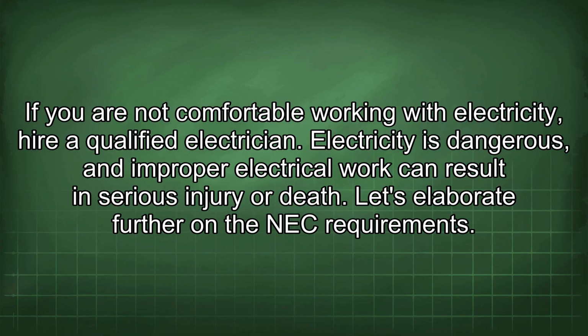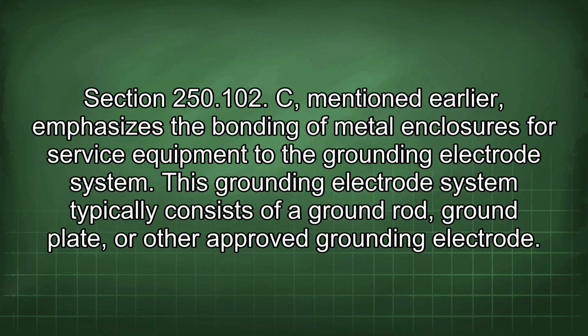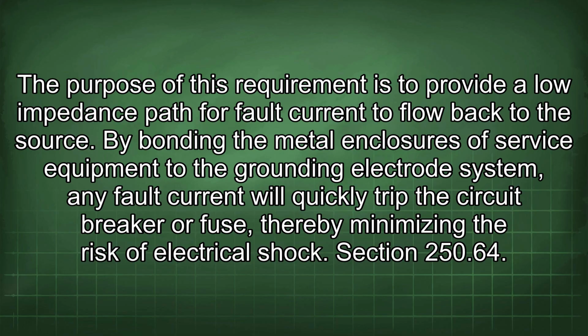Let's elaborate further on the NEC requirements. Section 250.102(C), mentioned earlier, emphasizes the bonding of metal enclosures for service equipment to the grounding electrode system. This grounding electrode system typically consists of a ground rod, ground plate, or other approved grounding electrode. The purpose of this requirement is to provide a low impedance path for fault current to flow back to the source. By bonding the metal enclosures of service equipment to the grounding electrode system, any fault current will quickly trip the circuit breaker or fuse, thereby minimizing the risk of electrical shock.